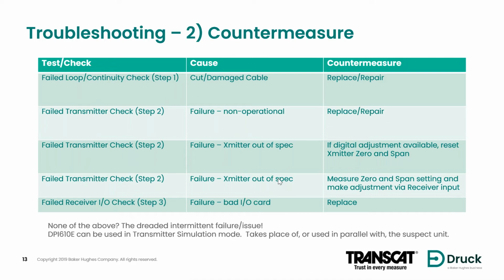So those are where the portable calibrator could come in very handy, not only in making those determinations and adjustments, but also when we step on to the confirmation step of troubleshooting, you can actually do a full calibration on the unit to ensure it's performing over its full range. Step 3, possibility of identifying a failure in the controls and the receiver. One possible failure mode could be a bad I/O card. It got zapped with an overvoltage, contacts corroded, whatever it might be. And then you could possibly repair or replace the I/O card that the transmitter is connected to. My note below, as I said before: it sounds strange sometimes to say, I hope we find a problem, but if you can identify a problem, then you can fix it, right? If you can't identify a problem, it's hard to fix.